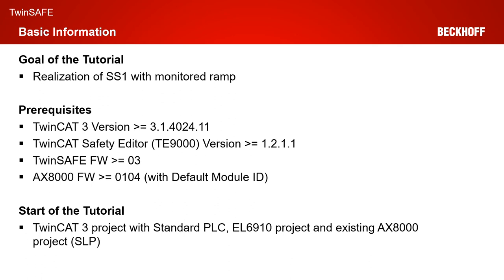As prerequisites you need a TwinCAT 3 version greater or equal to 4024.11, a TE9000 version greater or equal to 1211, a TwinSafe firmware greater or equal to 03, and an AX8000 firmware greater or equal to 01.04 with the default module ID active.